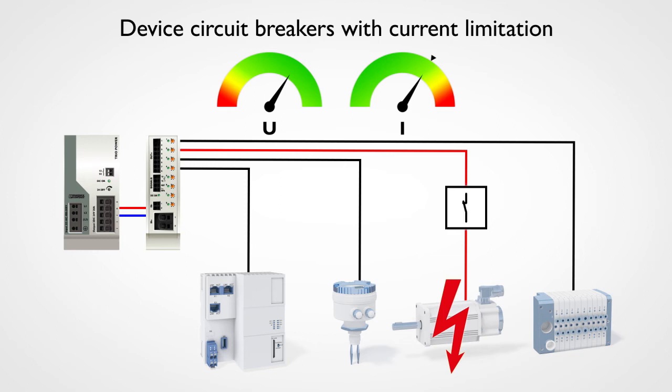Nevertheless, the device circuit breaker trips after a defined time, thereby disconnecting the faulty branch from the supply. In the case of a temporary overload, for example, due to an electric motor starting up, the device circuit breaker enters current limitation mode, but does not trip. It then returns to the normal operating state after the overload event has passed. The system continues running as before.